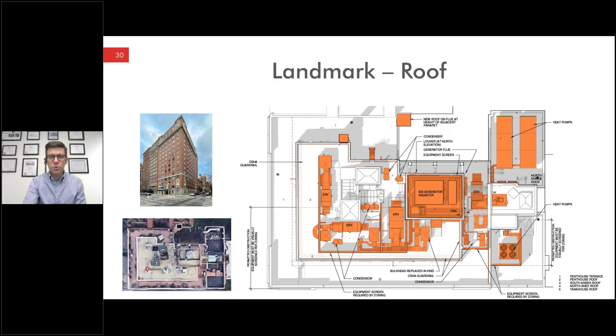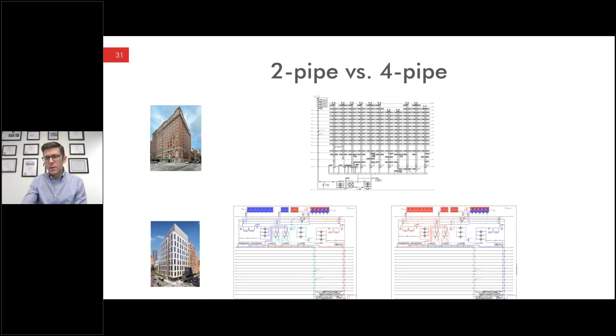Okay, I talked a little bit about this, the 2-pipe versus 4-pipe. Again, NYU, because of the program, allowed us to do a purely 2-pipe system, whereas at Weill Cornell, we have a hybrid: purely 2-pipe on the student residences, but a 4-pipe for the lower level amenity space. These are the risers. You can't see these super well, and that's kind of by design. I didn't want to go into too much detail here, but there are two key takeaways. The first is that the right-hand side of modules on the risers are the simultaneous heat pumps. That is allowing us to do simultaneous heating and cooling for some of those systems when we do have a simultaneous load from the 4-pipe system, whereas we do not have simultaneous machines at NYU because it is purely a 2-pipe system. So there is no simultaneous load given the 2-pipe arrangement. So that was one difference.